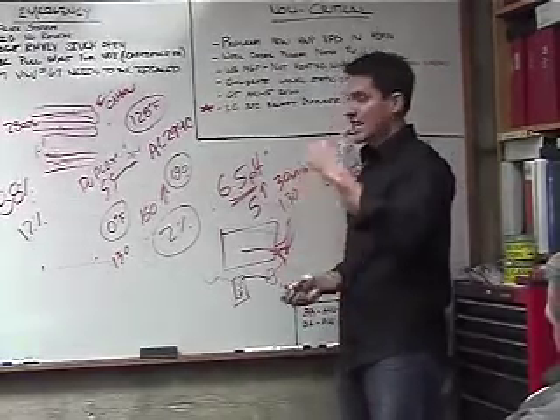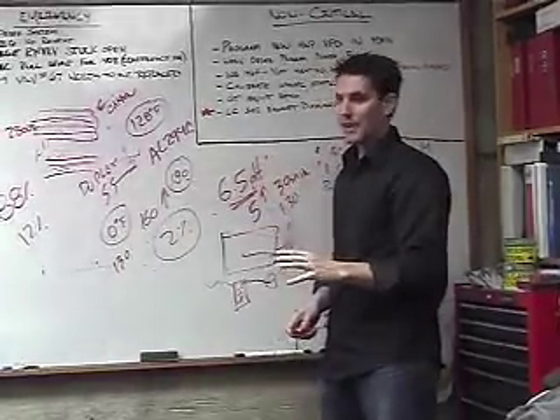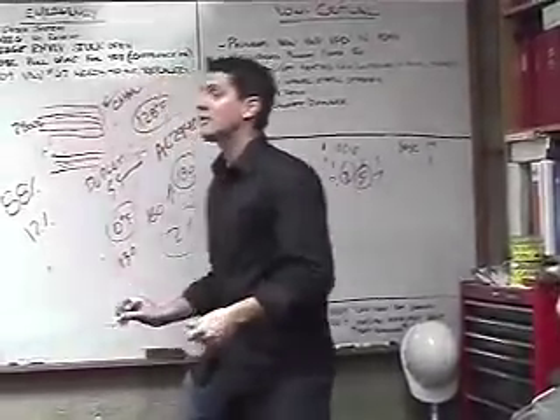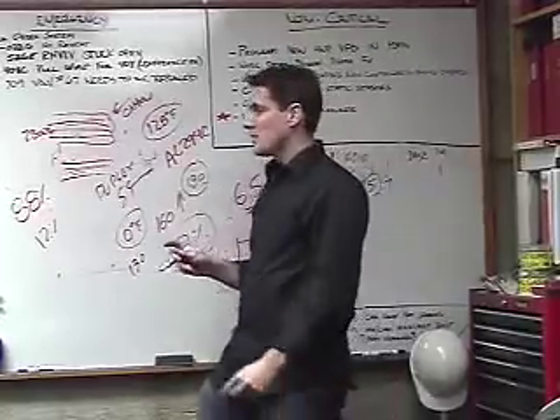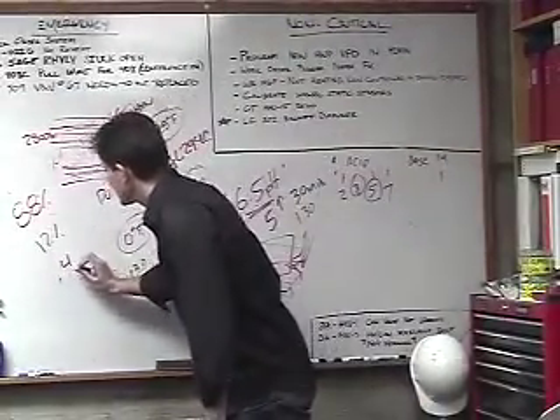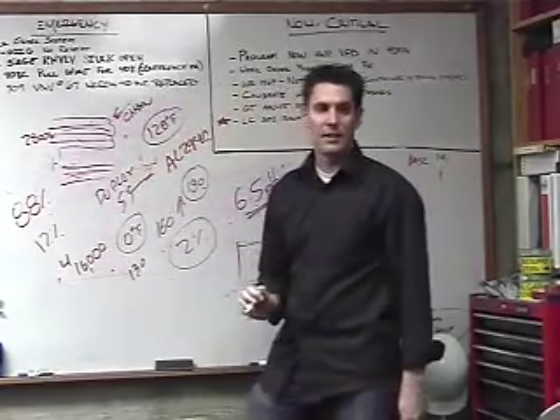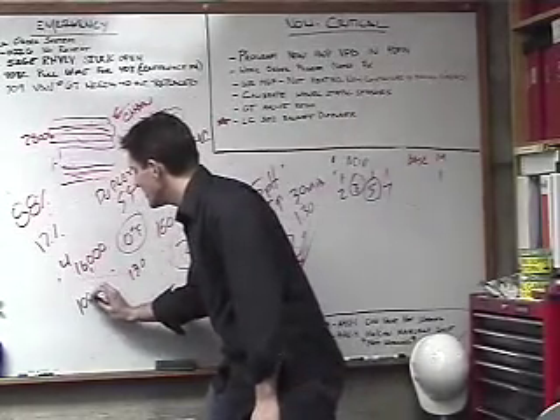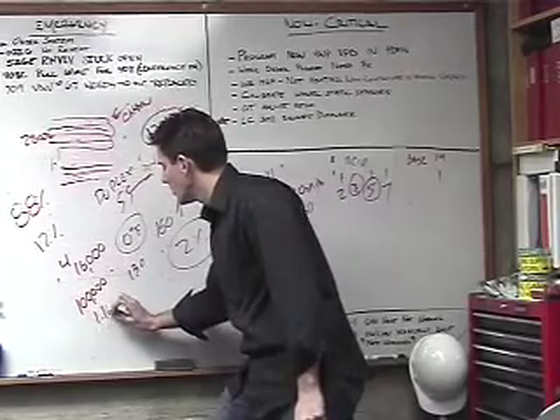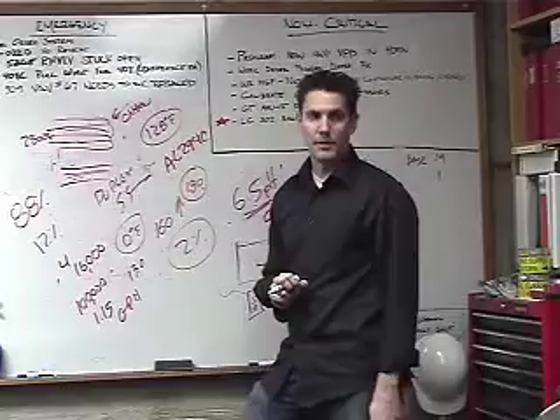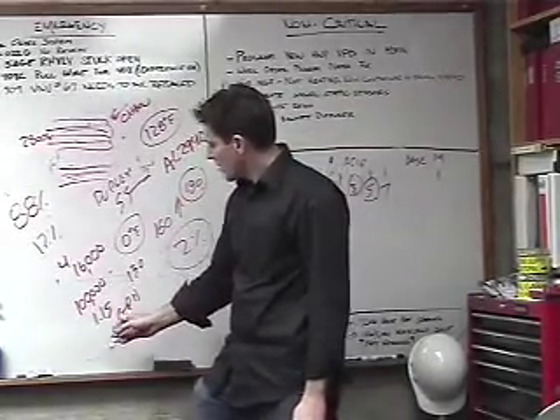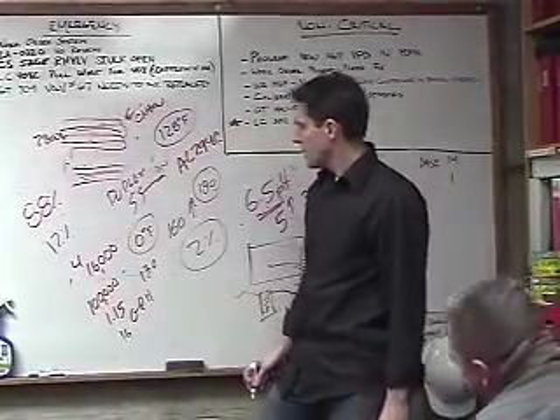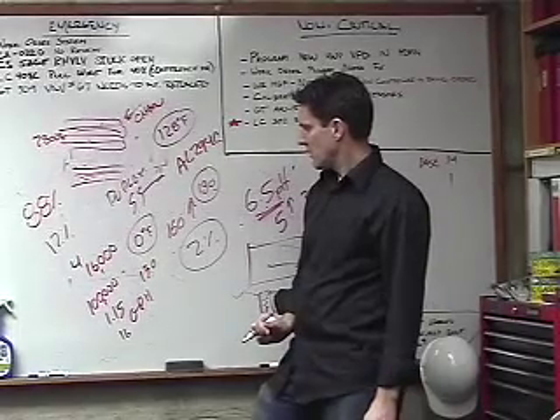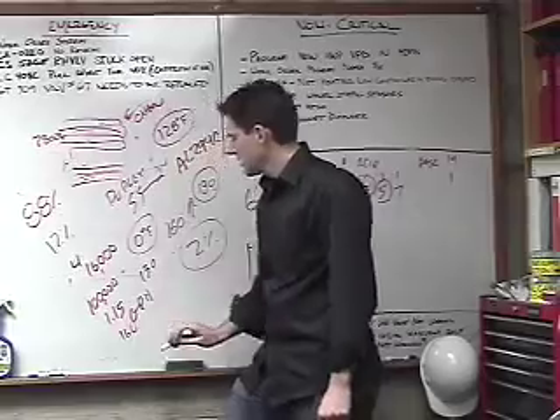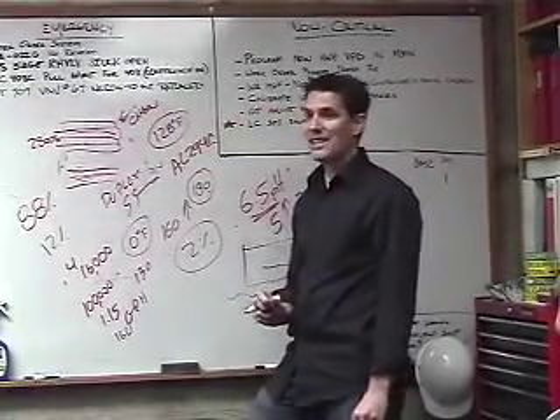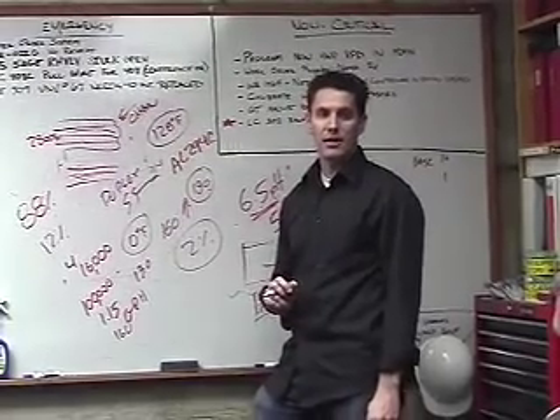Okay. Just to give you an idea of how much water vapor we create with natural gas. Anybody want to guess? Your boilers are 4 million? Okay, so you've got 4 million BTU boilers, so we've got 16 million BTUs out there that could potentially be running. Per 100,000 BTUs, you form about 1.15 gallons per hour of water vapor. So if we multiply this by 160, you're going to be at about 170 gallons per hour, potentially, of condensate flowing out of those things.